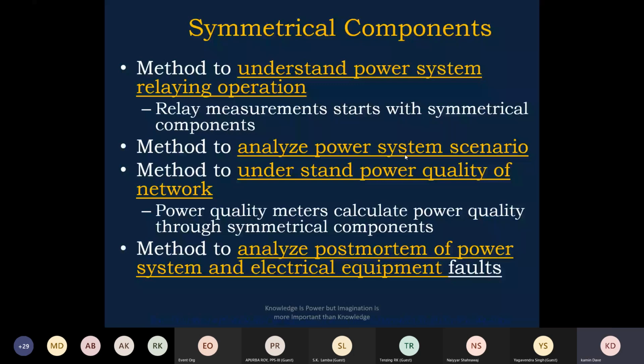slides. The voltage, current and impedance are converted into rectangular form, and then further into sequence components, and then the relay takes the decision whether it needs to operate or not. So it is a method to understand power system relaying operation, whether the relays are operating correctly or not, because the relay algorithms are based on these only.